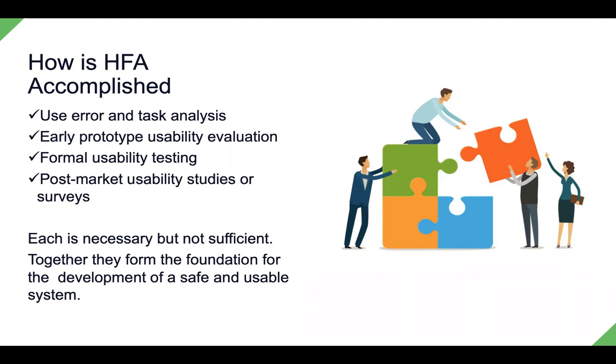This is product designers and product owners sitting in a conference room with a whiteboard, brainstorming how users are going to use their device to perform tasks, to analyze how they're going to get things done, how they might interact with the device. And even at this phase, you start to think about how they can make a mistake. What could go wrong here? And really start to use that to drive even your initial design.